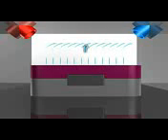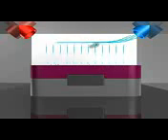These create a vacuum inside the sterilizing unit before the sterilization process begins. This means that air is sucked out and replaced by water vapor. This guarantees that the materials being sterilized are surrounded by water vapor on all sides, an important condition for sterilization.